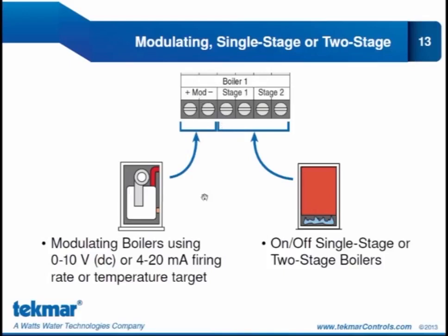The modulating output can be configured for a firing rate target using 0 to 10 volt or 4 to 20 milliamp output, or it can be configured for a temperature-based target with the EMS1 and the EMS2 configurations. EMS2 is what we use to control up to 4 Viessmann Vitodens 100 and 200 boilers.